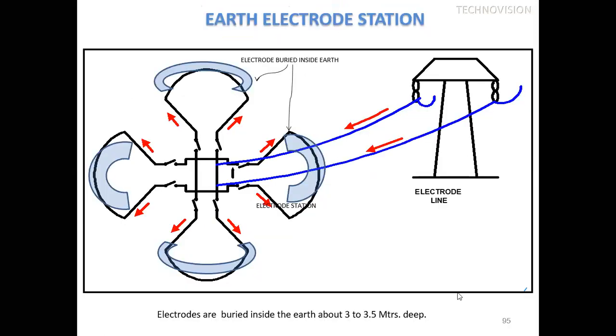So this is the electrode station. Whenever monopolar mode is on, in that monopolar condition, what happens? The return current goes through the ground, but before that it goes through the electrode line, and there are the electrodes which are buried 2.5 to 3 meters deep, and this current goes to the ground, and this area acts as a conductor. The property of DC, or any current, is that it always follows the least impedance path.